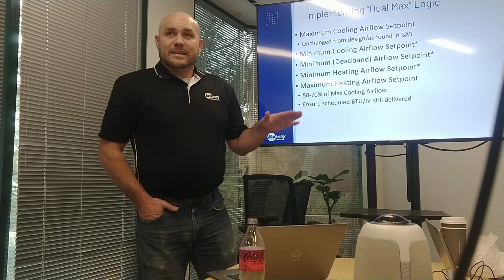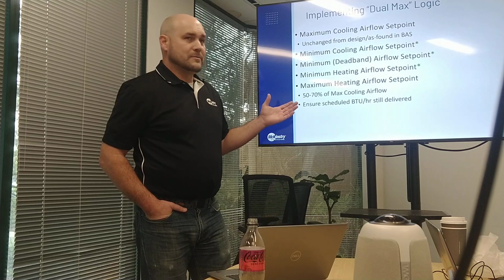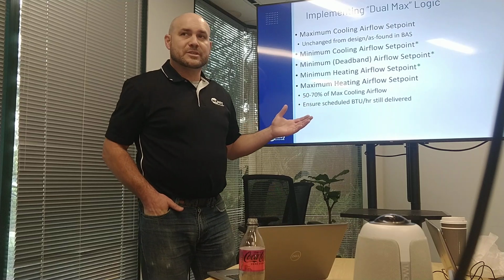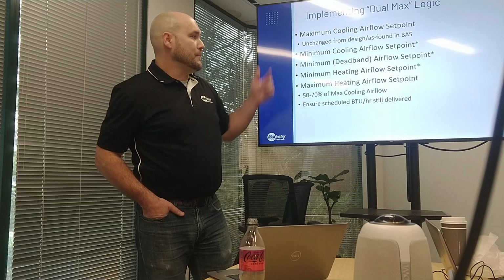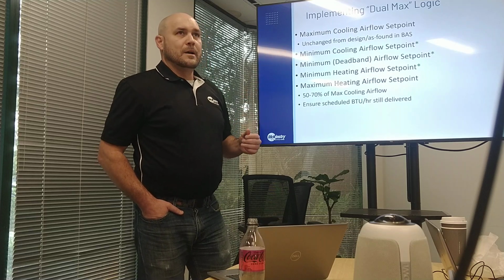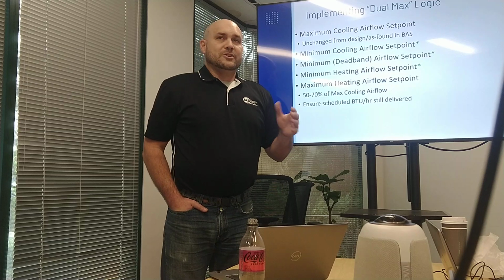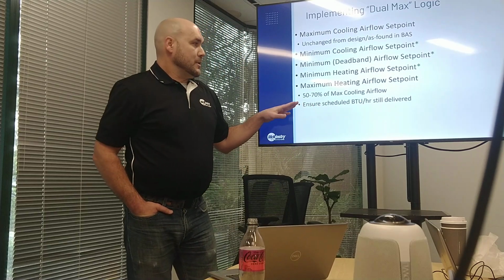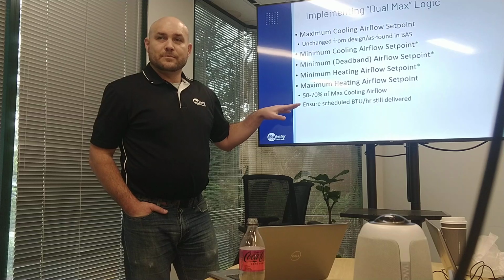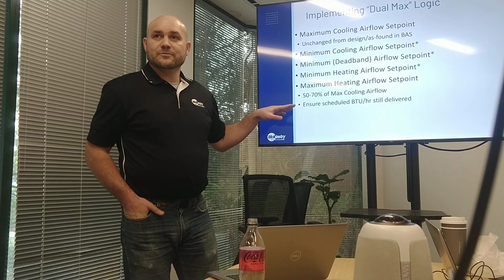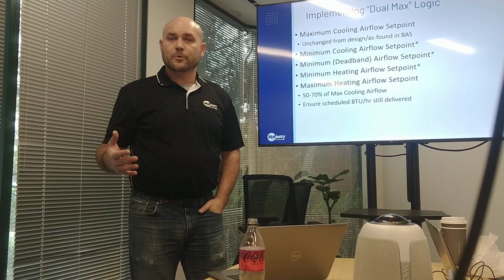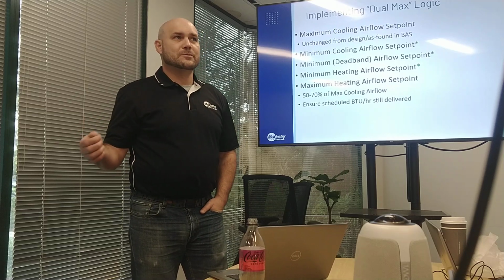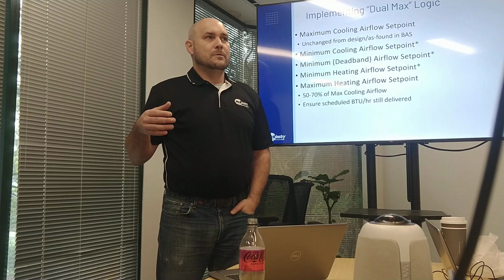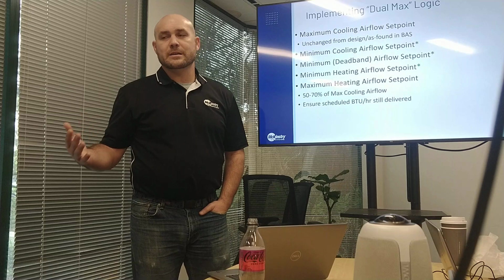I'll admit right off the bat that the heating maximum airflow is still a bit arbitrary. As a rule of thumb, it can be 50 to maybe 70% of the cooling design maximum. But the big trick is to make sure, through Guideline 36, that you're delivering the number of BTUs that the space requires or that the box is originally scheduled for, but that you're delivering those BTUs at no higher a supply air temperature than 90 degrees.